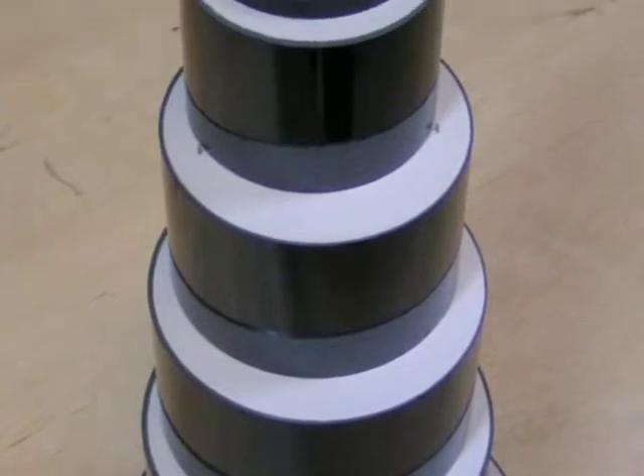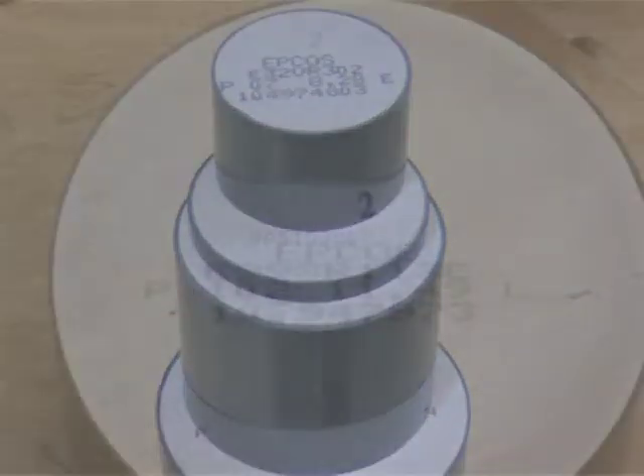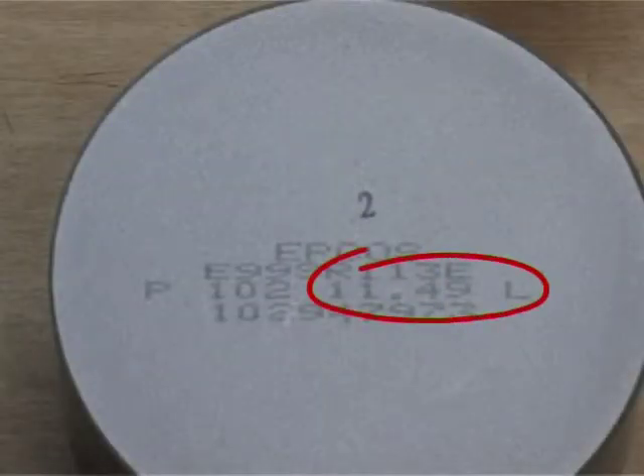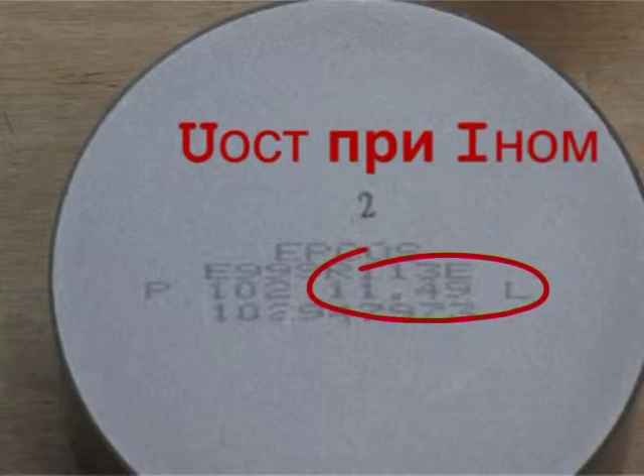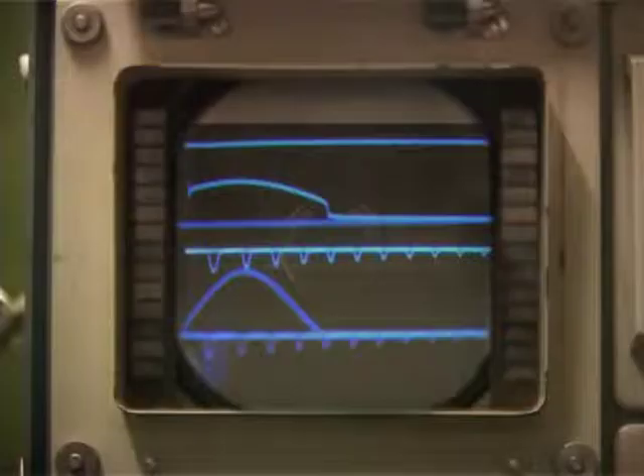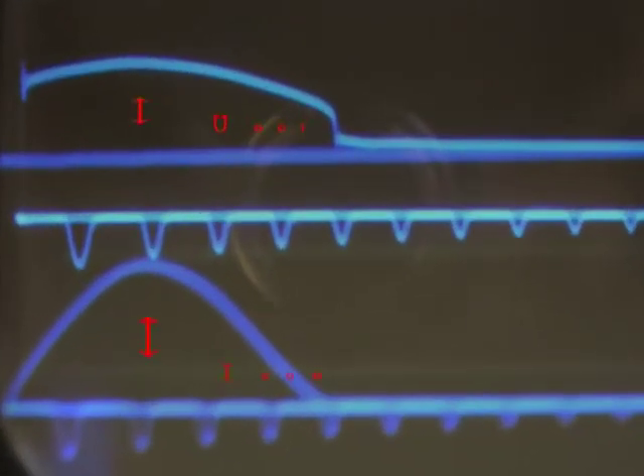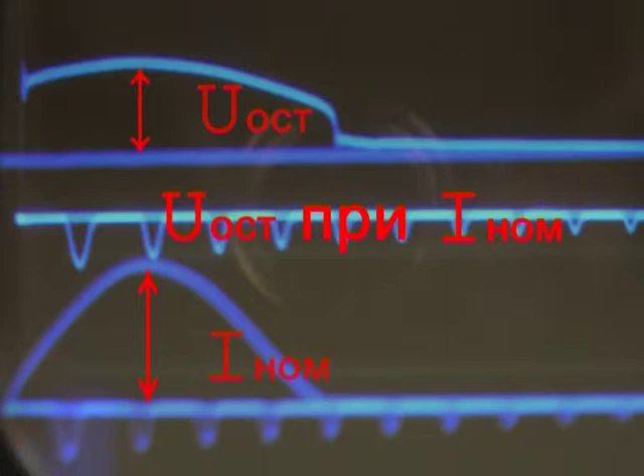Assembly of a surge arrester is done according to the residual voltage at rated nominal discharge current that is indicated on each varistor. These values on varistors are checked during entry control of each batch. During the first phase of surge arrester manufacturing, the necessary varistor columns are assembled according to specification and passed on to production.